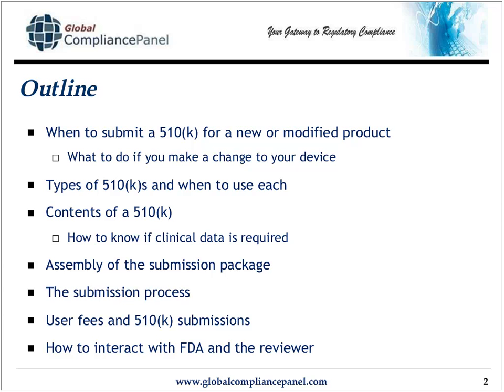When the agency started to challenge industry from a financial perspective, that was when a lot of executive management took a step back and said, well, now I'm going to try to determine whether or not I need to submit a new 510K. And that's when the guidance document titled, I'll paraphrase here, when to submit a new 510K came out, giving us in the industry marching orders, direction, as far as when we could or didn't have to submit a new 510K.